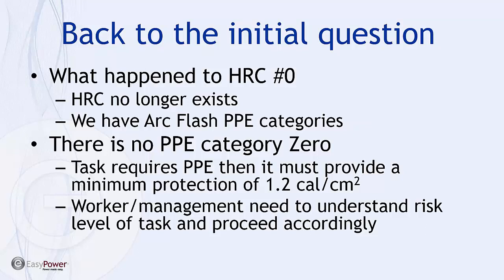It just means the level of protection can be relatively low. But if I'm working, even if the arc flash boundary is only 9 inches, and I have my face or hands within that space, I better have some protection on them. It's important to understand that and not ignore it, because using a reference point of zero implied there wasn't much going on.